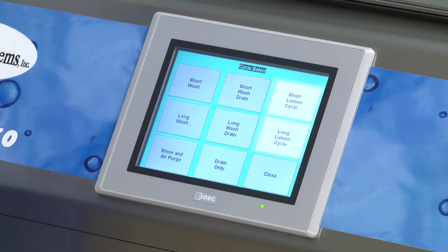Lumen cycles are for instruments that need to be flushed, such as laparoscopic, robotic, and orthopedic instruments. The short lumen cycle will wash for 8 minutes, drain, rinse, and air purge. The Long Lumen Wash will do the same but with a 13-minute wash.